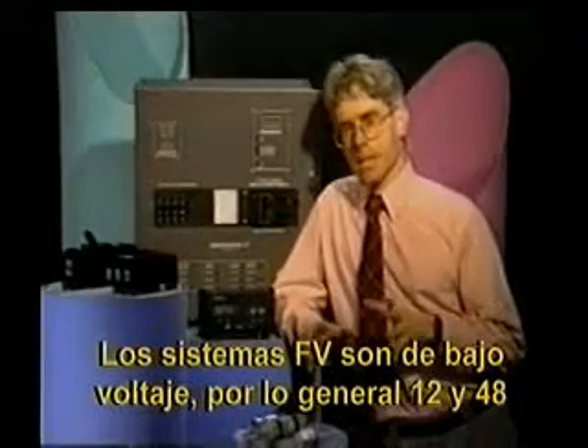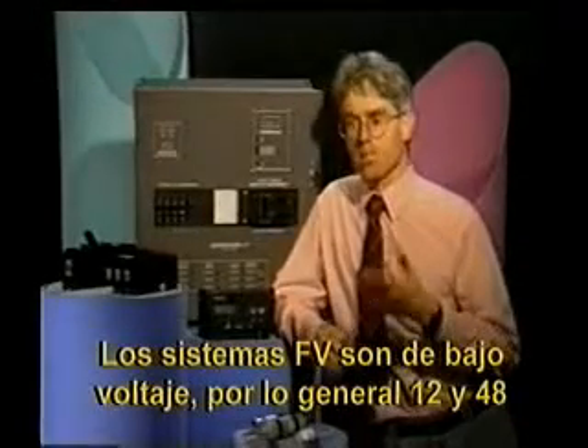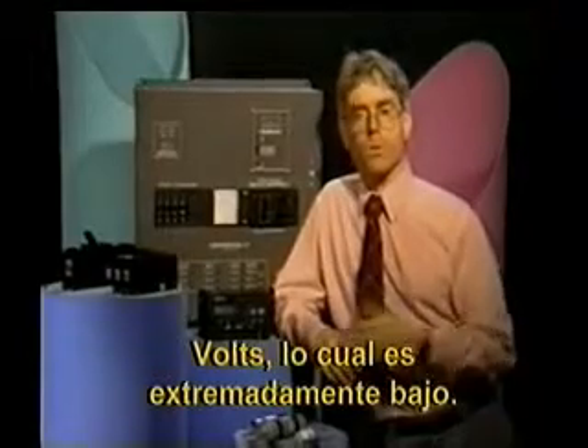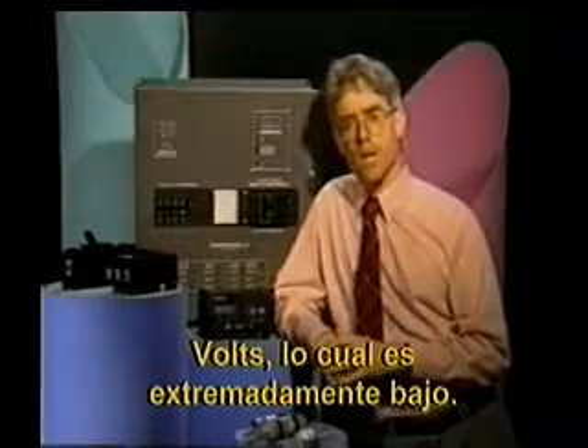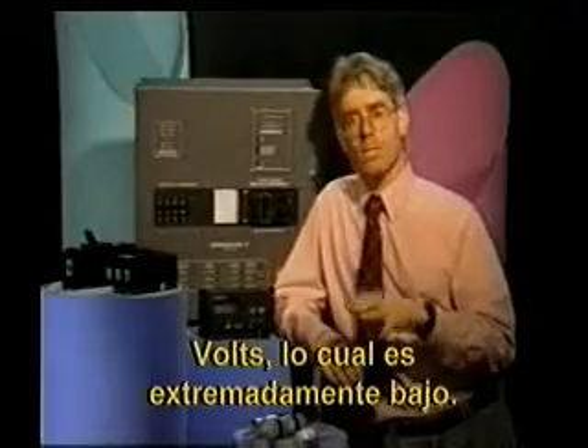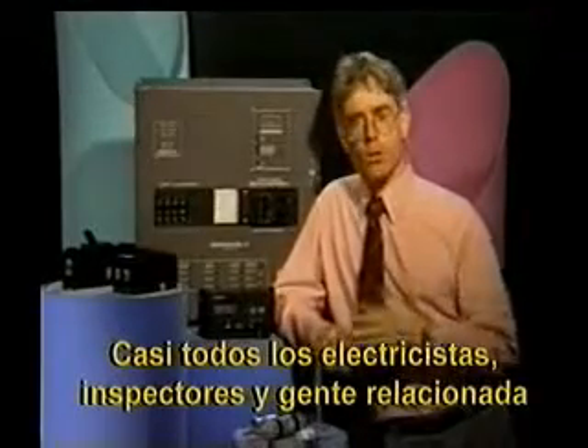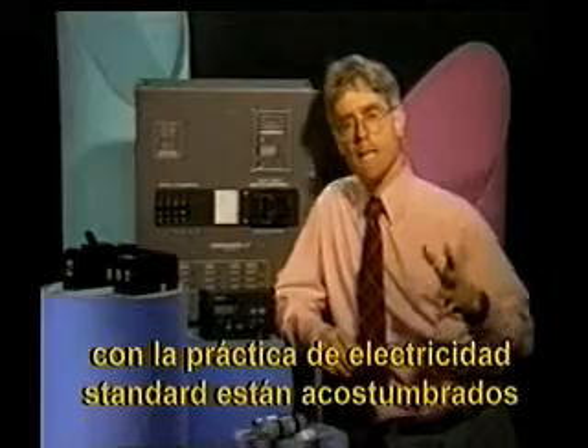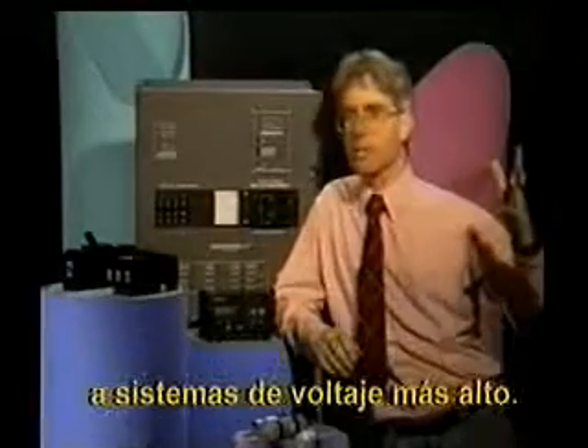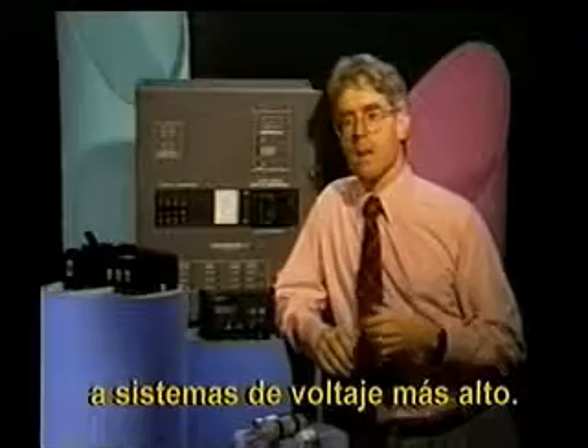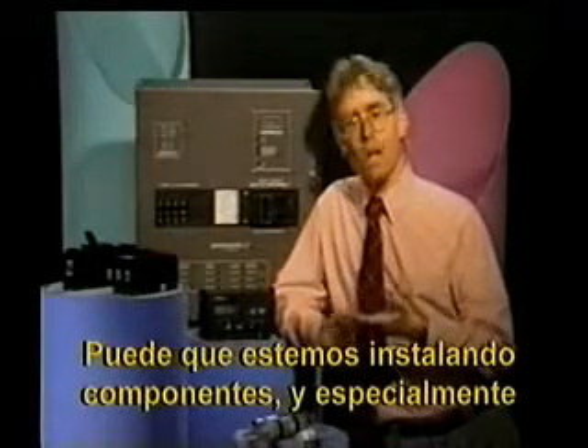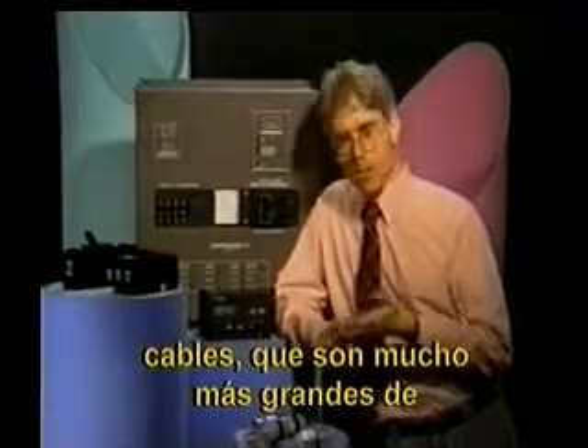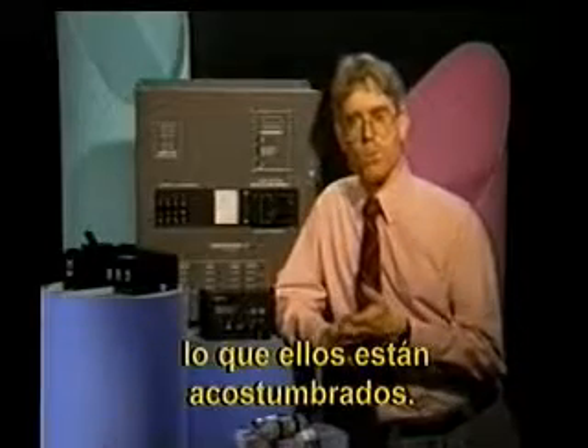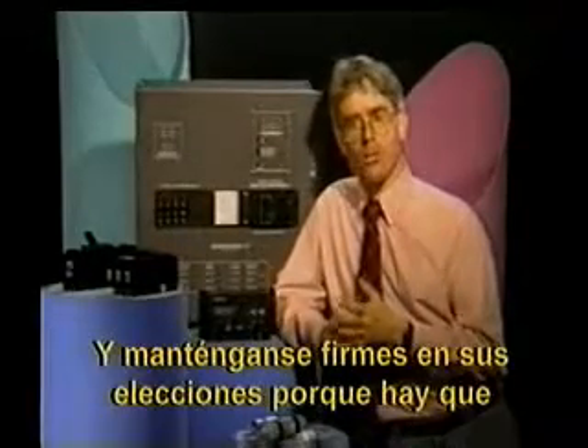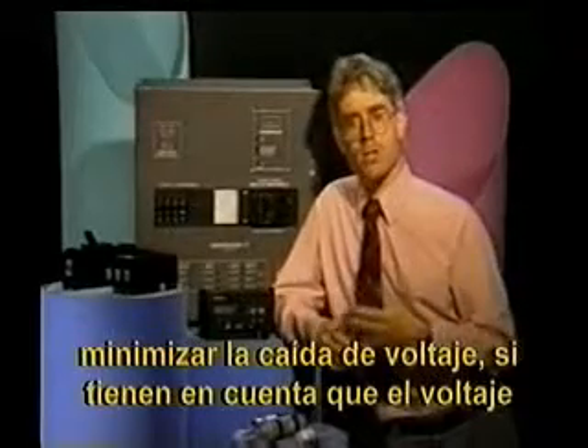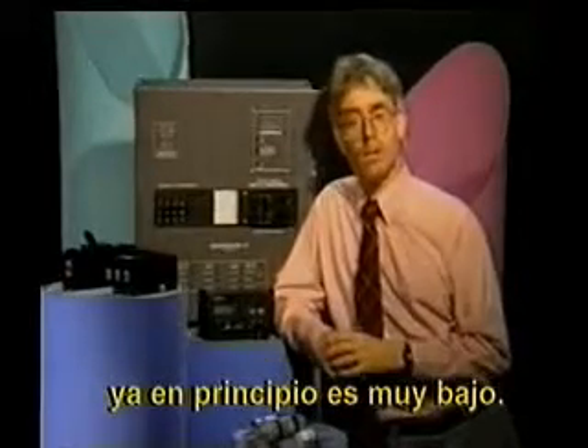In low voltage systems that we're typically dealing with in photovoltaics, 12 and 24 volts, perhaps 48, but 12 and 24 volts are most common. That's an extremely low voltage. Most electricians and inspectors and folks involved in standard electrical practice are used to higher voltage systems. We may be involved in installing components and especially wires that are much larger than they're used to. And I want you to stand firm in your choices for that because, of course, we have to minimize our voltage drop because we have such a low voltage to begin with.